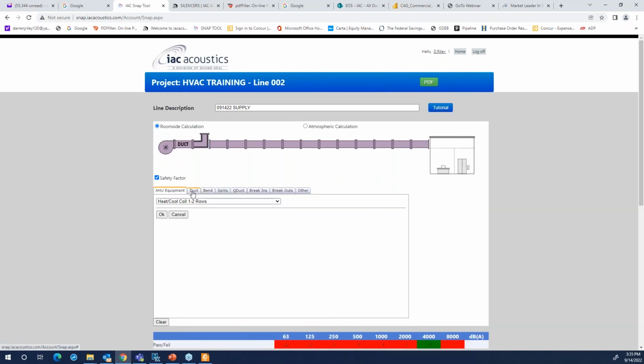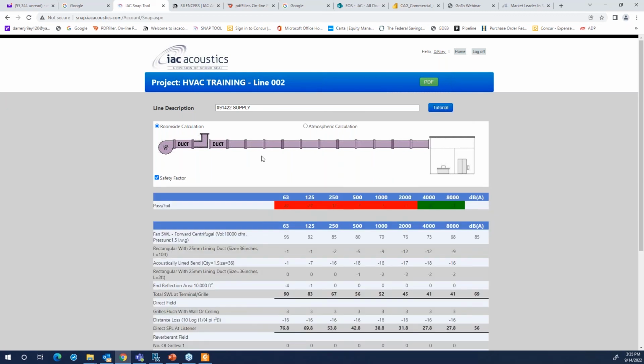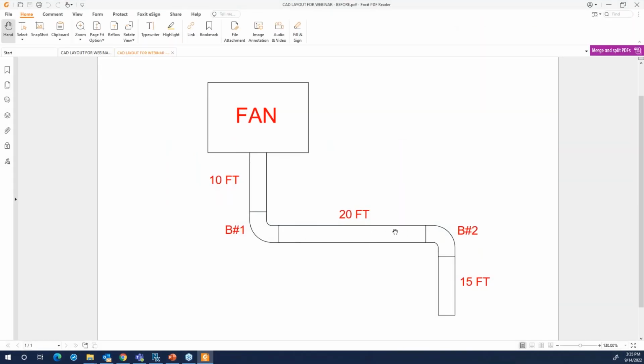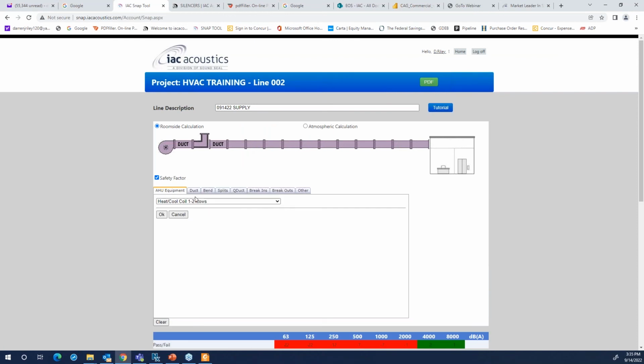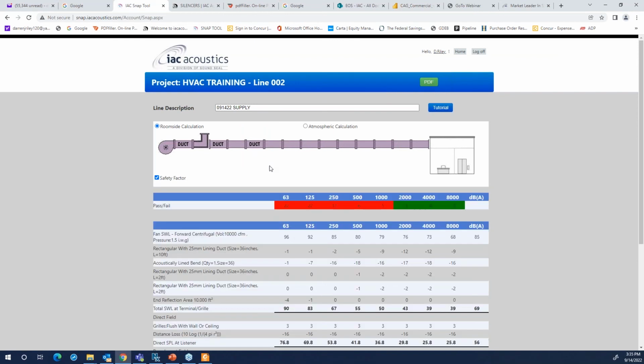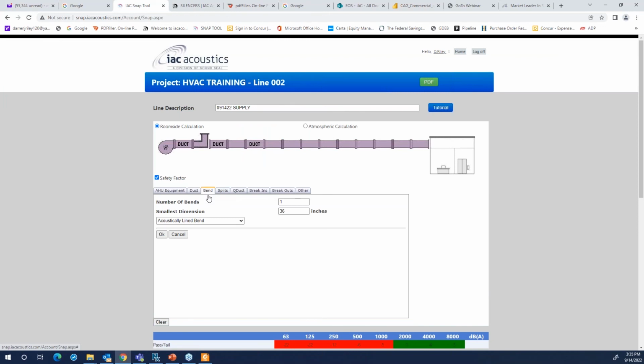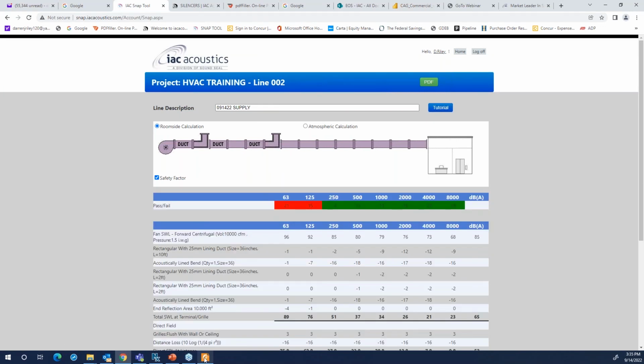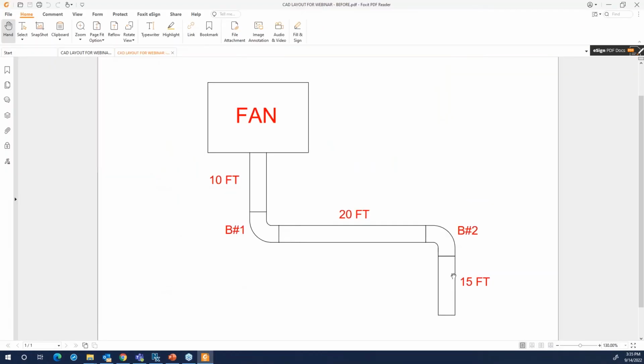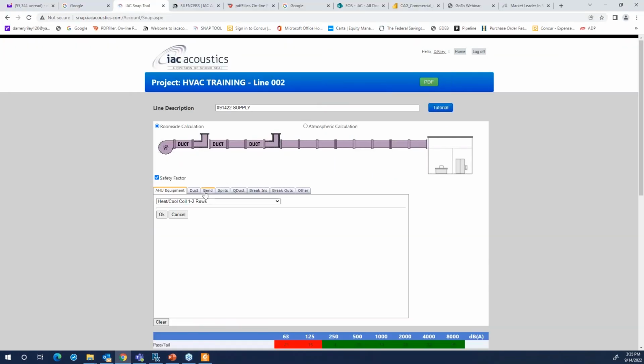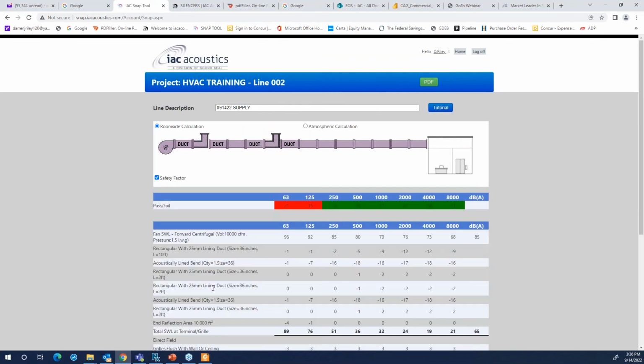Remember, 2 feet right after the bend. So I'm going to go ahead and insert 2 feet of duct right here. I'm going to skip right here because, again, we're working on 20 feet. So I'm going to put another 2 feet of duct right before that bend number 2. I'm going to throw in bend number 2. And remember, we have 15 feet here. I'm going to throw in 2 feet of duct right after this bend. So we have our system. We have the same system right here.